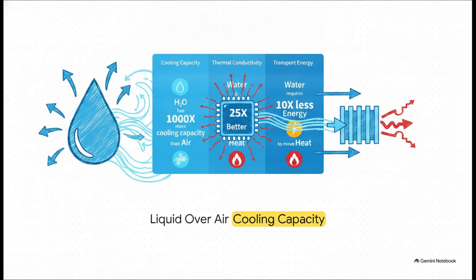And we aren't just talking about minor, incremental improvements here, these are orders of magnitude. Listen to this: water has 1,000 times more cooling capacity than air. 1,000 times. Furthermore, because it holds so much thermal energy, it requires 10 times less transport energy to actually move that heat away from the source. And when you look at thermal conductivity, actually pulling heat out of the chip, water is 25 times better. This is exactly why future generations of hardware won't just benefit from liquid cooling, they're going to absolutely require it. Air cooling has simply hit a brick wall.